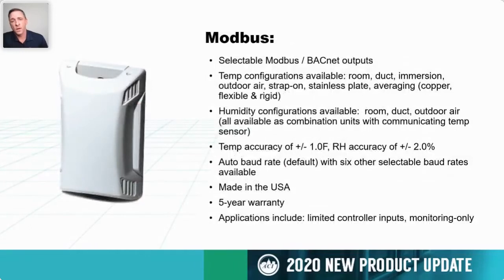Third on the new product list is the expansion of our communicating sensor line. Previously, we offered temp and humidity sensors with BACnet MSTP, and they were available in room, duct, immersion, and outdoor air configurations for temperature, and then room, duct, and outdoor air for humidity. Well, we're adding a Modbus option to that, so it's a user selectable or field selectable option, so you can select between either BACnet or Modbus.